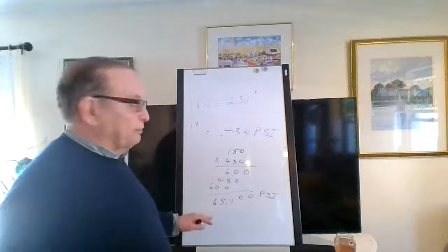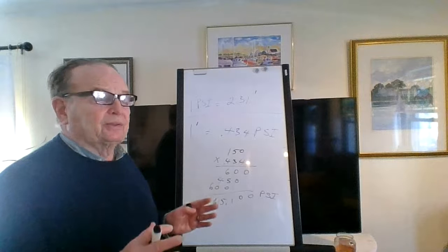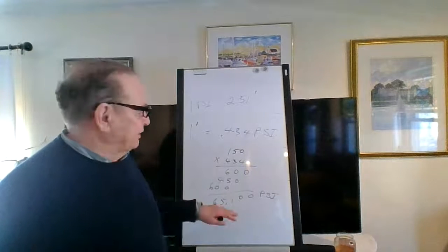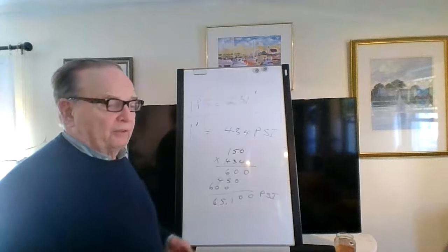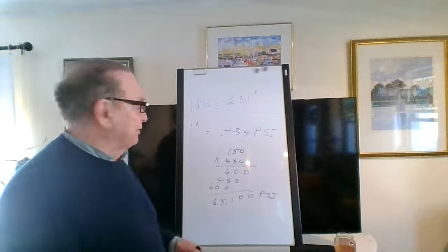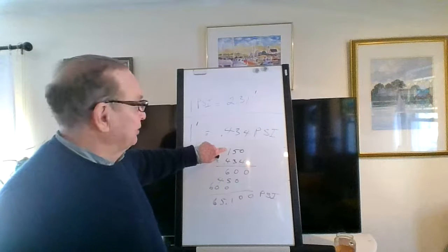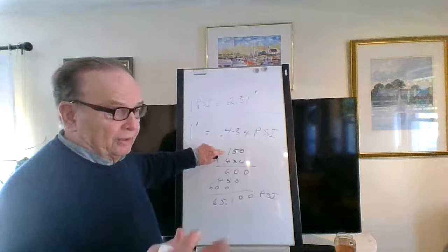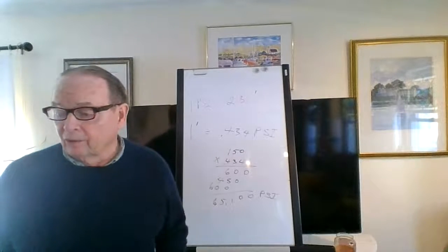That's a good pressure. If I had to set a pressure in my own house, I'd like something around 60, 65. Nah, 65 is more than enough. Okay, but that's a good pressure. Going to give you a good shower. You don't have to wait a half an hour to fill up your sink or whatever it is you're doing. Okay, so 150 feet takes 15 stories. That's 10 feet per story is the average to get that. But that's the one in the book that you're looking at on page 105, and that's how you find it.